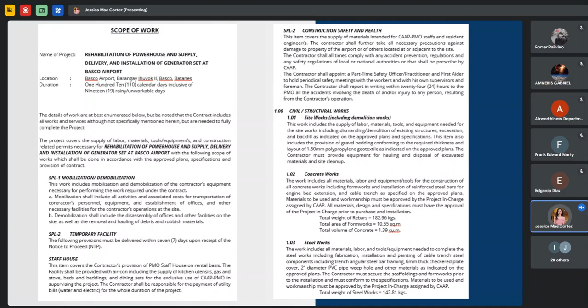For the electrical works, it includes the installation of feeder conduits and fittings, feeder conductors, installation of panel board, and installation and provision of emergency power supply, which is one set of a 100 kVA silent-type diesel engine generator set.